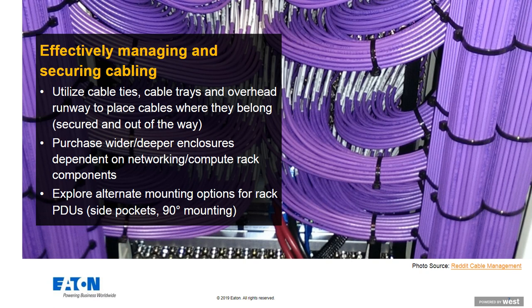The next thing is you want to effectively manage and secure cabling. This can be data cabling and power cabling. Looking at the photograph here, that's what I would call a nicely dressed data cabling cabinet, where everything's cable tied nicely. The bundles are held very straight. By keeping everything cleanly routed like that, it makes it easier when there is a problem to try to trace down some sort of trouble. The other thing it does is facilitate airflow because you're not having such a mess of cables. You have spots where the air can transfer through.